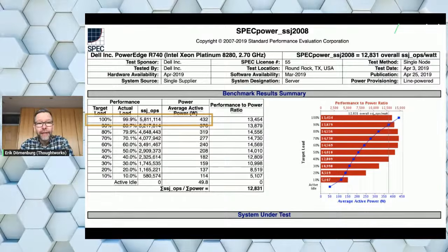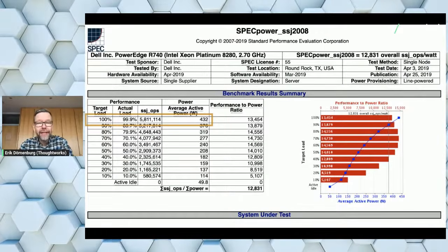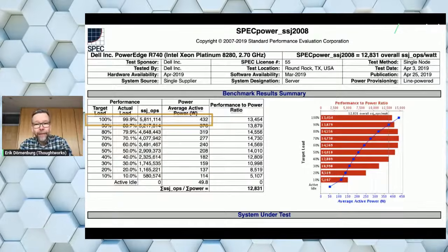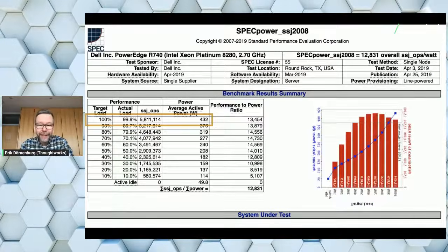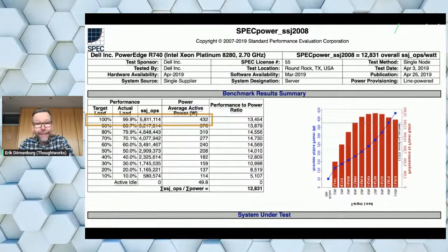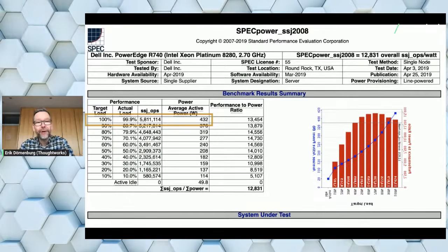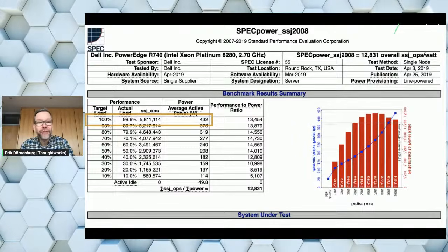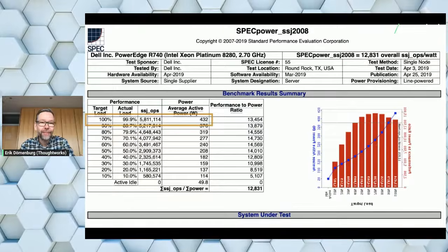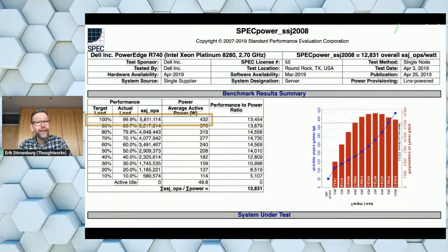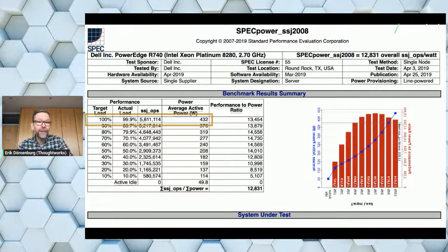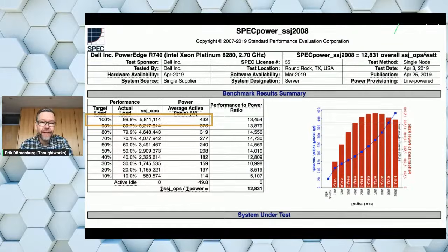It is, though, shown in the SPEC Power database with the X and Y axes flipped. And I've done it here, because you can't read the text anymore, but you can now see the proportionality here of how much electricity is actually being used. You can also see that the curve is not linear and that the best area of efficiency is not necessarily 100%.